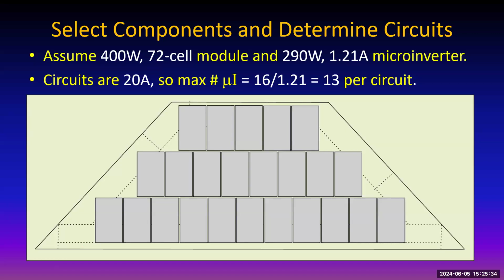So microinverter, we're using microinverters with 1.21 maximum output current. So to stay less than 16 amps total for a 20 amp circuit, because we need to have the circuit wiring and overcurrent protection at 125% of the total maximum output current from the string of modules. That means you can't have more than 13 in a circuit. Very straightforward. Simply divide 16 by the output current of 1.21, and that means you can have 13 of them.